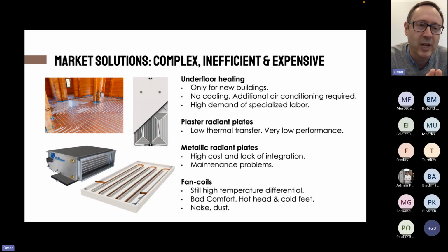Every project where underfloor heating has been accomplished perfectly, we basically get a very similar result, mainly concerning heating. But the problem with underfloor heating is that we have to refurbish all the buildings in Europe, and once you have someone living there, it's very complex and very costly to introduce a radiant system in the floor. And because most of the time they are not executed as they should be, they are not suitable for active cooling. Basically, the mortars or concretes that you use for the radiating slab have low thermal conductivity, and as we will see later on, to provide cooling you will always have the dew point as a limitation to power the system.